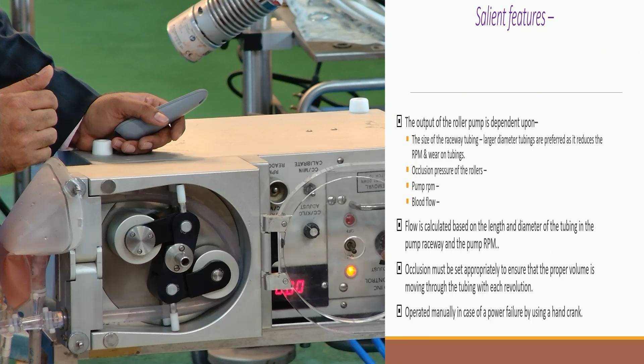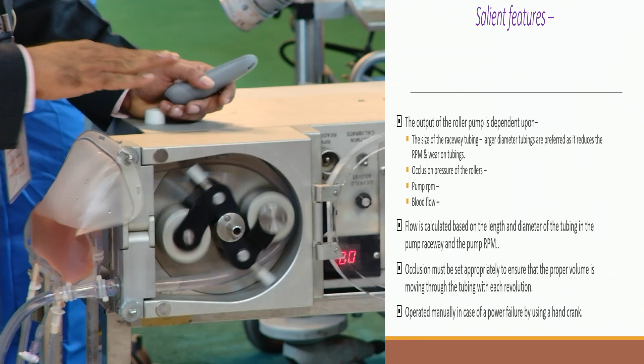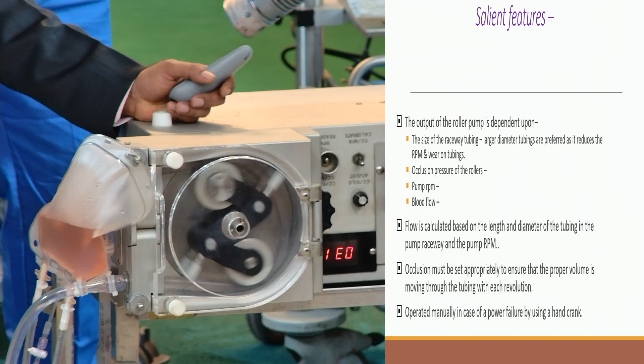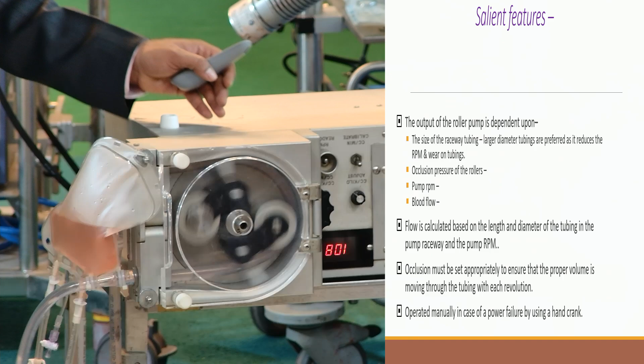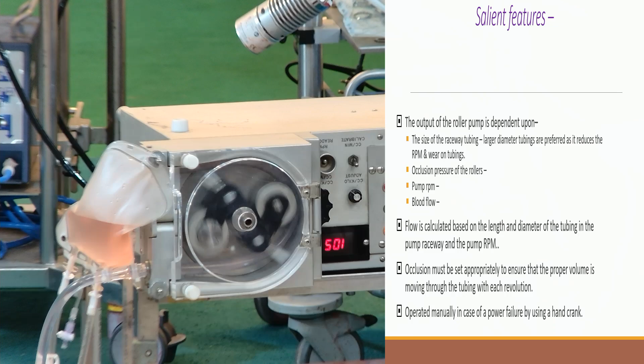Okay. So this is the way the pump moves and it displaces the water. Okay. See, can you see this? And if you suppose the return line gets blocked somewhere, it will create lot of positive pressure and it will rupture this tube. So this is the roller pump. ECMO and everything started basically with a roller pump first, and then we moved on to centrifugal pump. Okay.